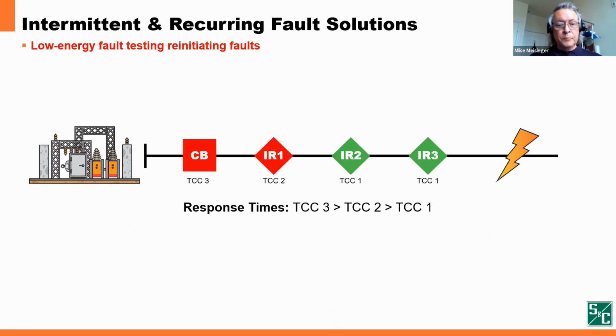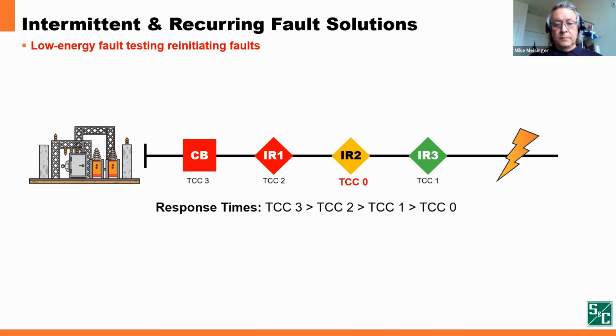Next slide, please, Clever. So here again, we have the same one line as we did before, and the fault that reinitiates has initially caused both IR2 and IR3 to trip. Again, IR2 and IR3 are set to the same TCCs. We've done this intentionally to improve the segmentation of the feeder. Okay, next slide, please, Clever. So now, instead of just pulsing or just low energy testing and closing, we're going to low energy test. But when we close, we are now going to use a faster TCC. So TCC 0 is faster than TCC 1.